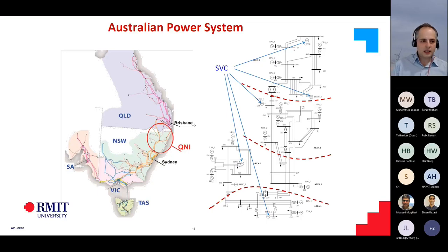This particular interconnector was stability limited for probably, I think, half the time throughout the year. So the operators weren't able to operate this link at 100% capacity because of the stability limit. By applying these types of controllers, we were not only able to stabilize the system in the event of a fault, but also able to increase the transfer capacity of that transmission line, which was really essential, especially during times when we have low inertia in the system.